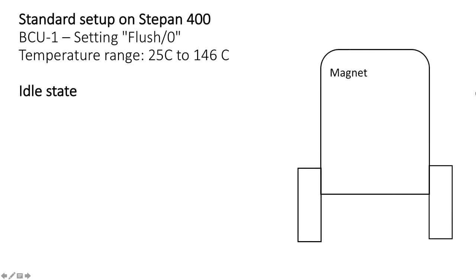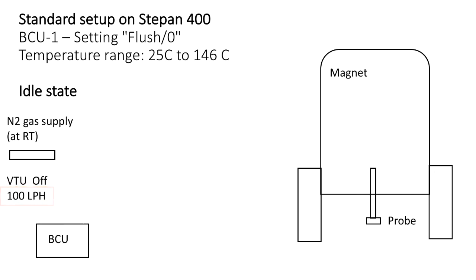In the idle state, we have a magnet and a probe and the supply of room temperature nitrogen gas. VTU is off and supplies instrument with 100 liters per hour of gas, which first directs to the BCU, Bruker cooling unit, which is currently off in a flush or zero position, essentially just supplying room temperature gas to the probe. The probe passes gas towards the heater. The heater is off and it supplies room temperature air to the sample. This is how we work at room temperature.